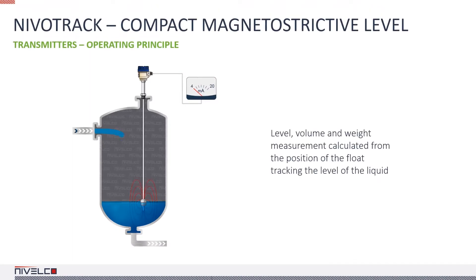Let's begin with the most accurate of them all, the Nivotrack Magnetostrictive Transmitter. It uses the magnetic field of a float sliding along a hollow stem containing a waveguide made from a ferromagnetic material. The assembly is suspended in a measured liquid. As the float moves, the field of the permanent magnet inside the float changes the alignment of the magnetic molecules of the waveguide in the stem.